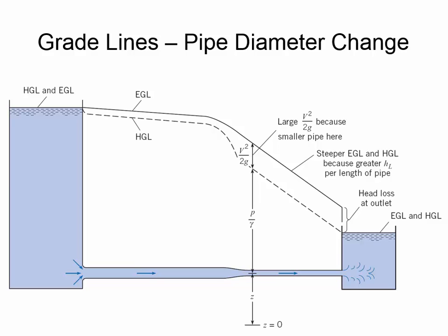And we'll do this a lot in hydraulic engineering when we're being really meticulous to identify all of the losses in a system. We will account for what's called an exit loss. When a pipe connects to a reservoir or a tank, all of the kinetic energy that it had in the form of velocity head is lost when the pipe discharges into the tank or reservoir.